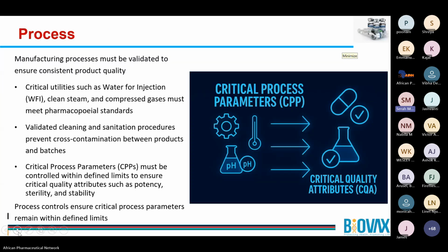So in terms of the process, I think I've already talked about this in my previous slides, but manufacturing processes must be validated. It's very important that we validate these processes to ensure consistent product quality. Underline that word, consistent product quality, because that's really the challenge. You can have the product of the right quality in the beginning, but if you cannot demonstrate that several batches or several lots after that have the same consistency or the same quality, then your system has a problem. It is not controlled, as we indicated earlier. So critical utilities like the water for injection, the clean steam, pressurized gases, they must meet pharmacopoeia standards. Like I mentioned, this area is highly regulated. You will definitely find a standard that will tell you the quality requirements for each of these utilities.